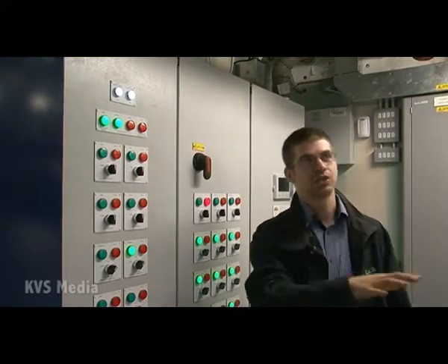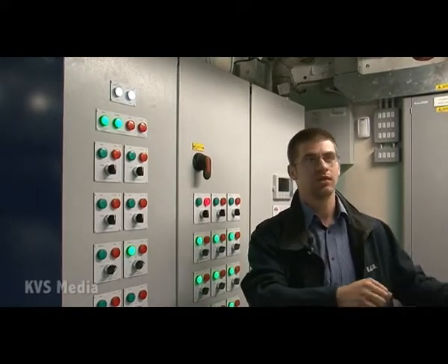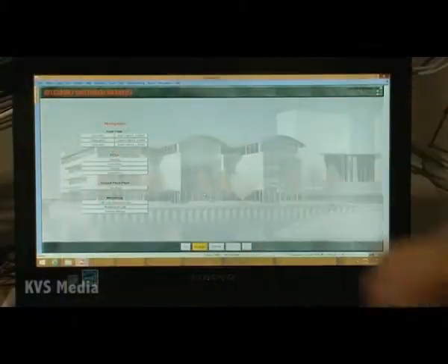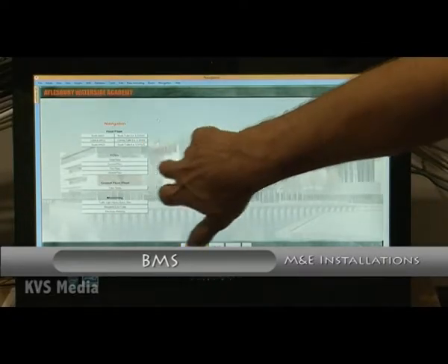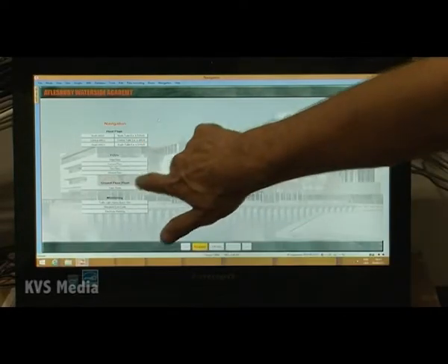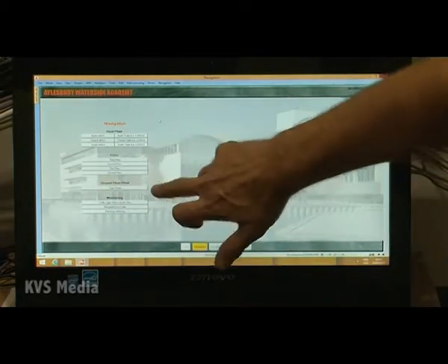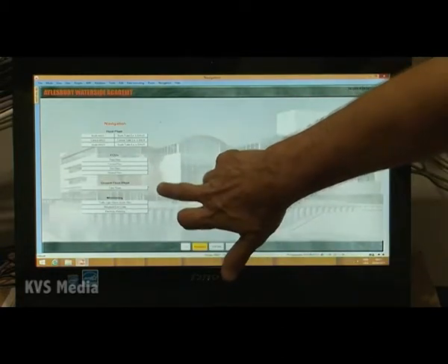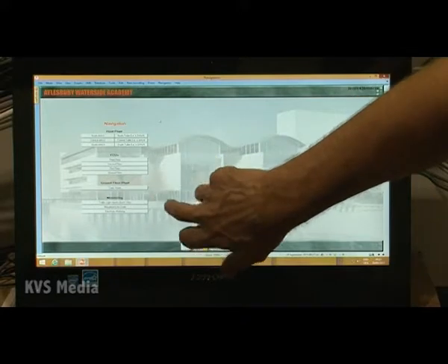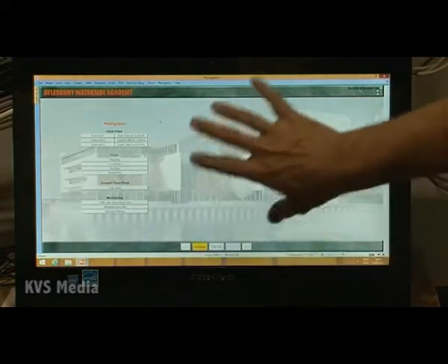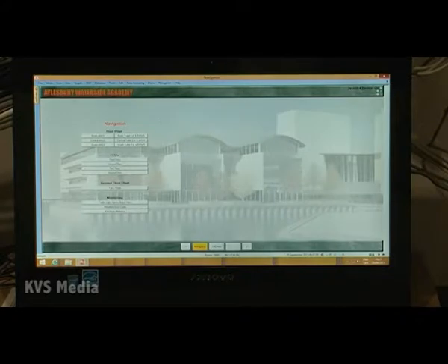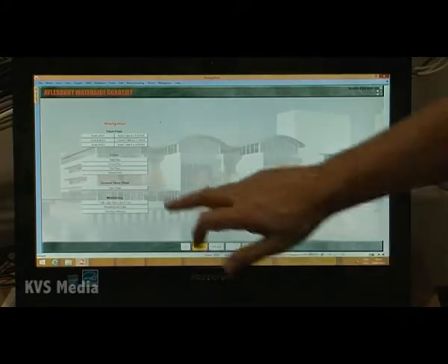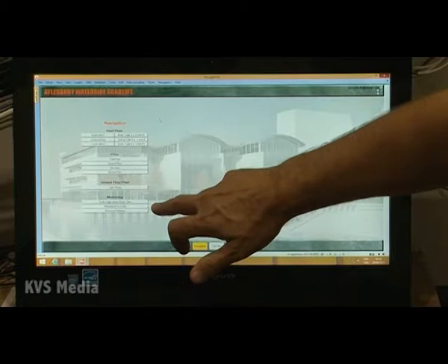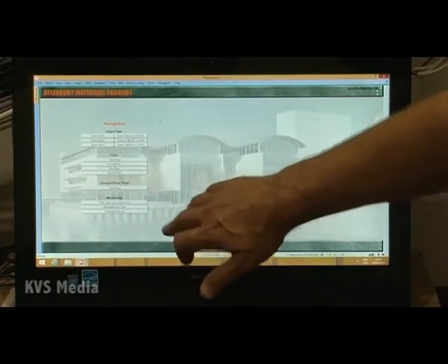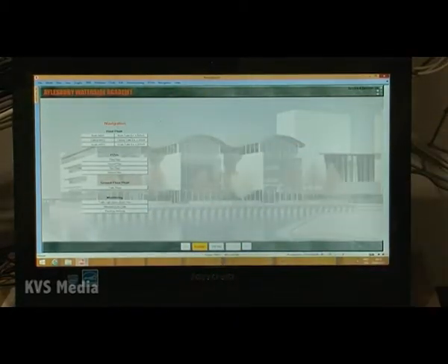There's some fire detection equipment in here above the boilers if flames are detected. So this is the main navigation menu system. You've got your air handling plant in the roof plant rooms at the top. Interface to the Mitsubishi system showing all the fan coil units. We've got another panel down in the tank room with some ancillary monitoring, and then we've got the traffic light alarm system showing reds and greens for healthy and fault. Same kind of thing for the Mitsubishi system, and then some electrical metering information. So I'll go through from the top.